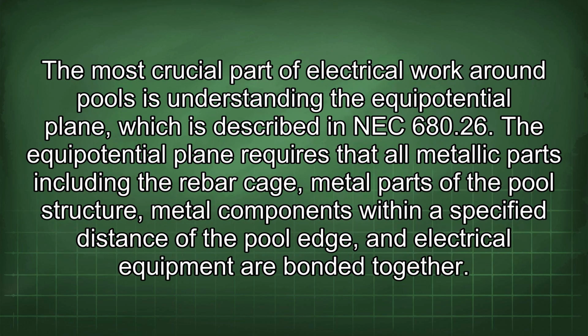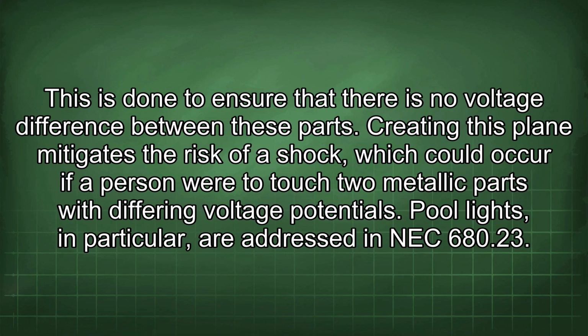The most crucial part of electrical work around pools is understanding the equipotential plane, which is described in NEC 680.26. The equipotential plane requires that all metallic parts, including the rebar cage, metal parts of the pool structure, metal components within a specified distance of the pool edge, and electrical equipment are bonded together. This is done to ensure that there is no voltage difference between these parts. Creating this plane mitigates the risk of a shock, which could occur if a person were to touch two metallic parts with differing voltage potentials.